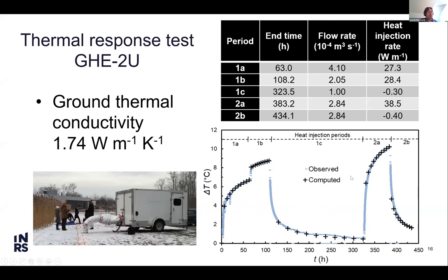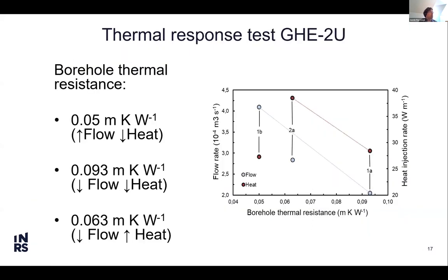Analysis of this test, fitting observed temperature with computed temperature using the line source model, gives us a ground thermal conductivity of 1.74 watts per meter Kelvin. So it's pretty much the same as what we had previously for our other borehole that is close to this site. So it's good, our test is reliable. But in terms of borehole thermal resistance, the results are quite interesting. For a high flow rate and a low heat injection rate, we get 0.05 meter Kelvin per watt. And this is what is shown on my graph here.